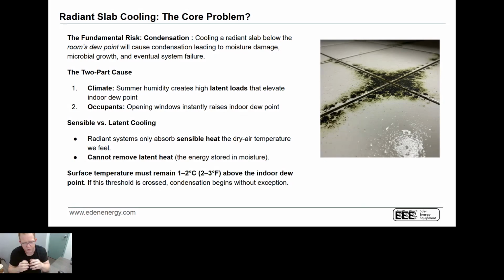We're going to walk through this at a very, very high level. But the reality is that you can design the perfect system, somebody leaves the windows open, and the perfect system comes to flaws if you don't have a backup plan. So the problem we're faced with is that when we're cooling a radiant slab, if we drop below the dew point, we're going to have condensation, moisture damage, and microbial growth, and eventually we're going to have a very, very big problem. We don't want that. It's a two-part cause, right?